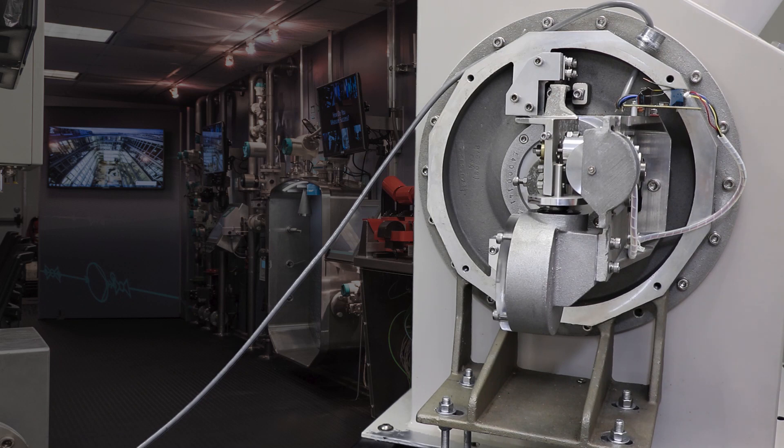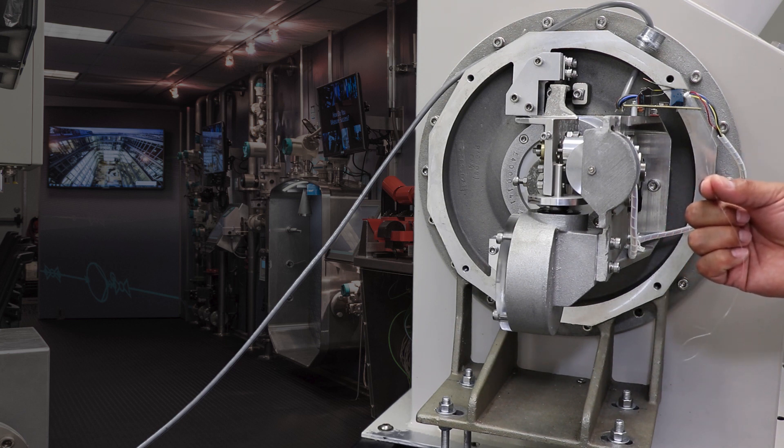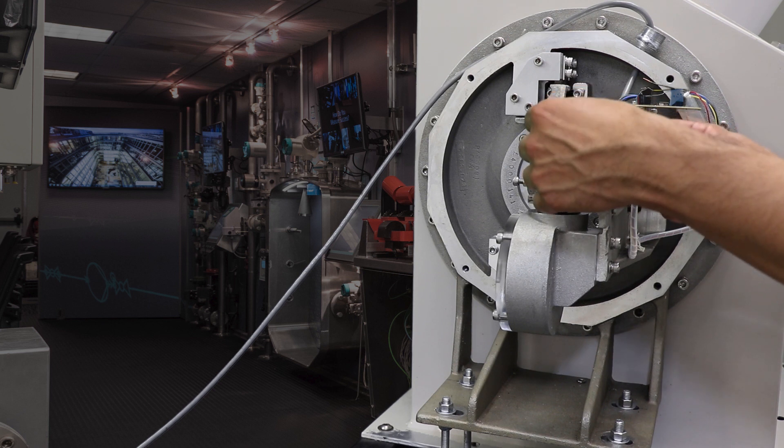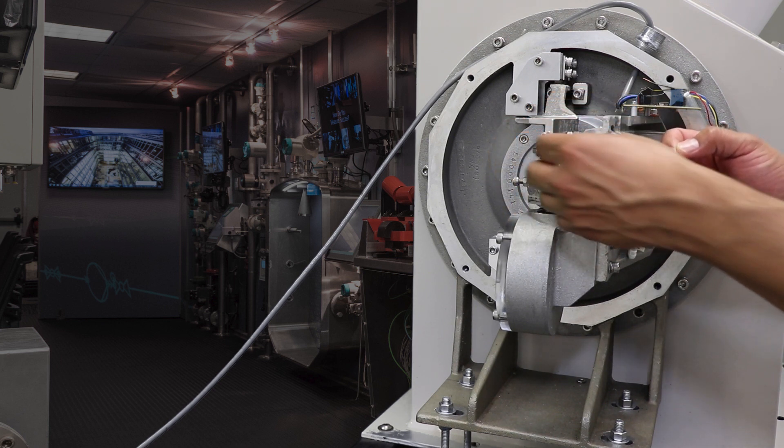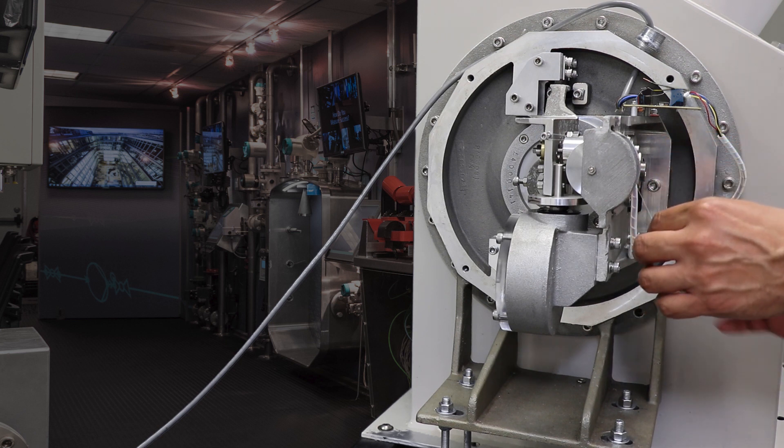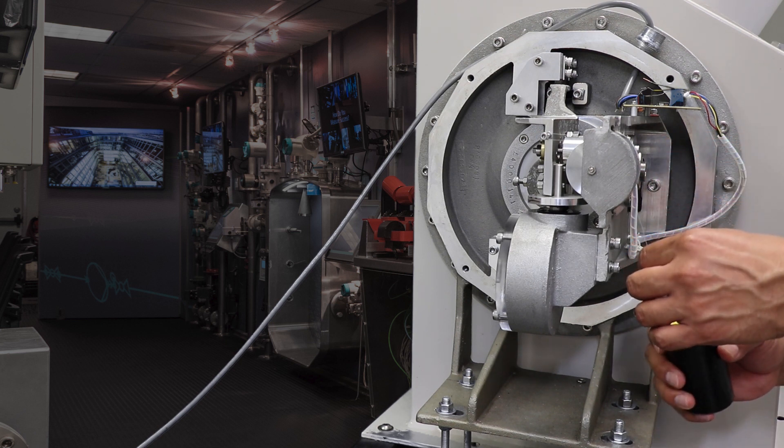When spanning, you must add a test weight. On this flow meter, you will need a string, preferably fishing line, to hang the test weight on. You will attach the string onto the bolt where the slot is and then over the calibration wheel and attach the test weight.